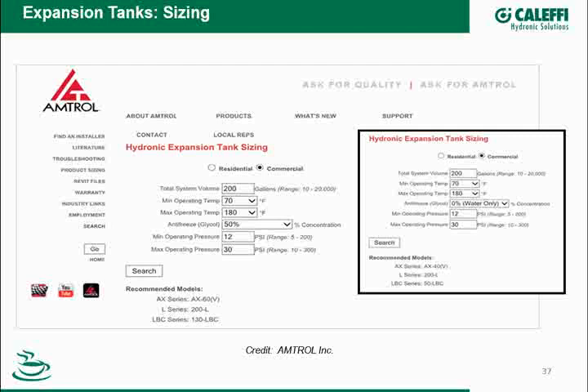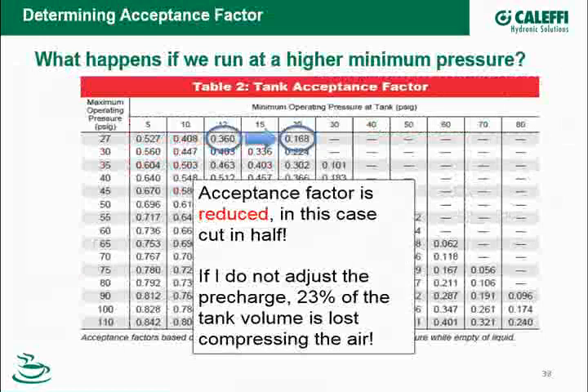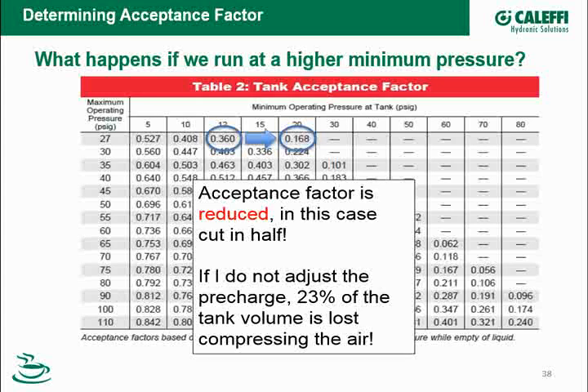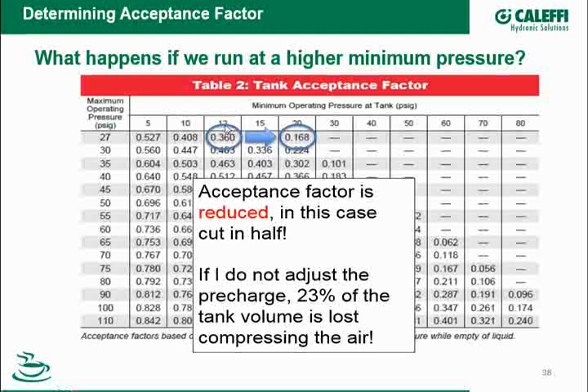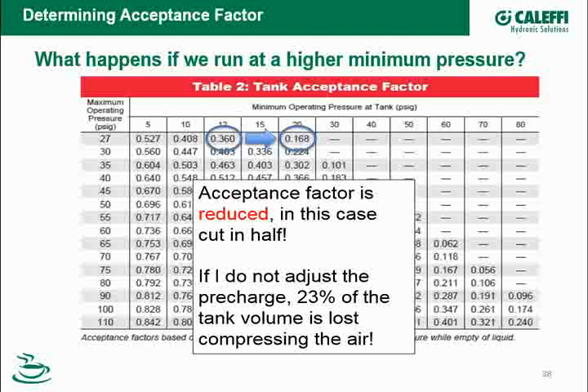Now, another thing that has to be considered, and I've seen this a couple of times on the wall, people start to talk about operating pressure, and they say, well, you know what? I typically don't run my systems at 12 psi. I run them at 18 or I run them at 20. There has to be a little bit of a concern on how that changes the dynamics of the expansion tank. Because if I go from 12 psi to 27, you look at that number there, I will be using 36% of that tank's volume holding the expanded water. If I go from 20 to 27, that 36% drops down. I'm going to round up to 17%.